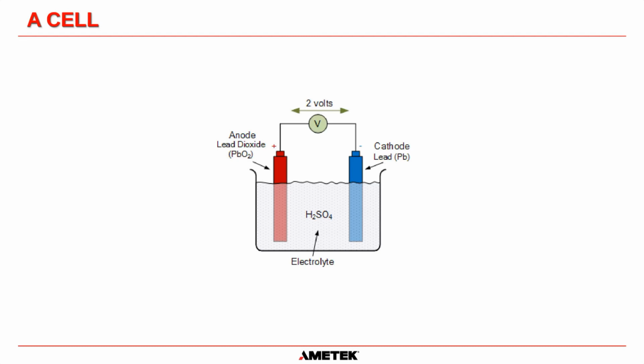On the left, we have the red anode, which is the positive plate, which is lead dioxide. And on the right, we have the cathode, which is the negative plate, which is, in most cases, pure lead. Those two plates have to sit within a diluted sulfuric acid mixture called electrolyte. Without electrolyte, the battery will not work. That is how the ions move between the plates and create electric current. As you can see at the top there, if this battery was fully charged, you would measure approximately 2 volts on a fully charged cell that is open circuit, that is, not on charge. We'll get to this in a moment.